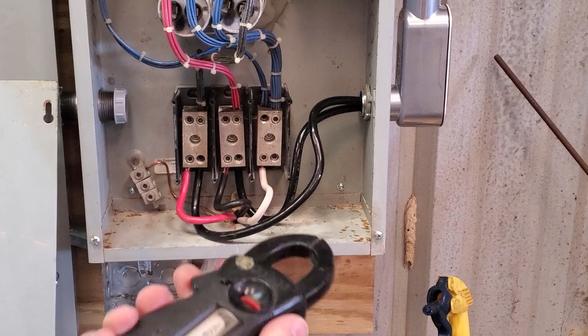Now that's real interesting. So if this thing is only drawing 12 to 13 amps on the supply, where does the 25 amps, 30 amps, and 40 amps come from? Let's check some voltages.